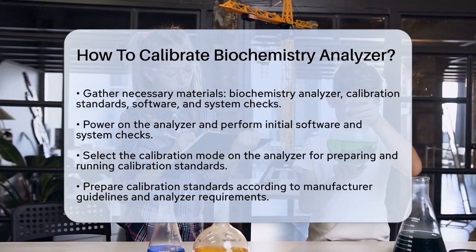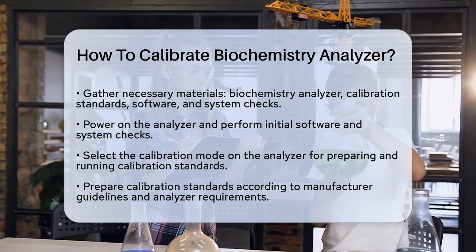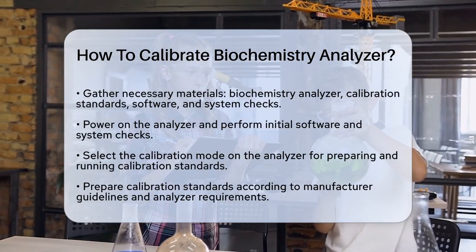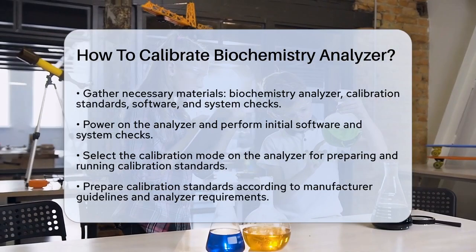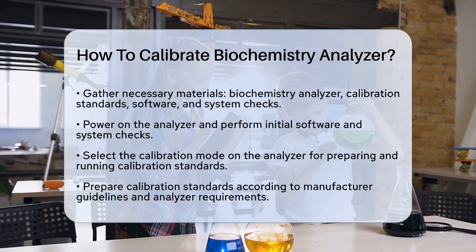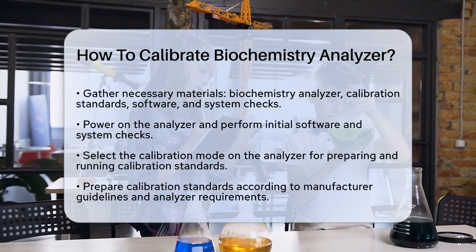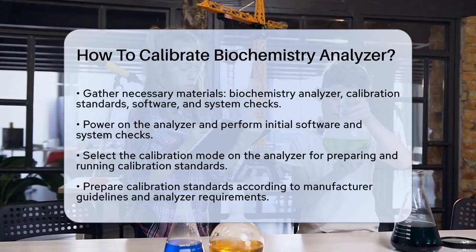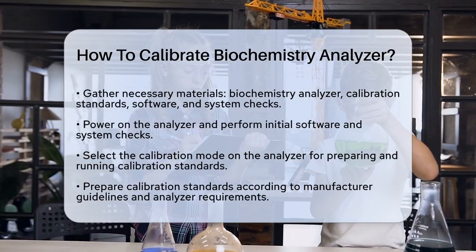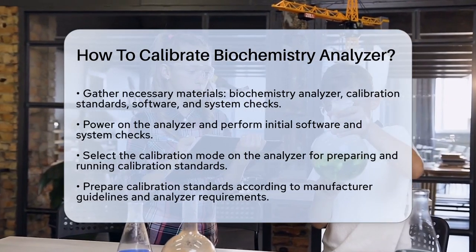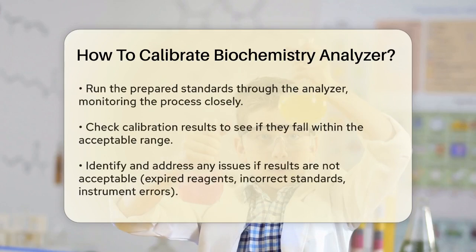Next, select the calibration mode on your analyzer. This mode allows you to prepare and run the calibration standards. These standards are reference materials with known concentrations of analytes that help set the accuracy of the analyzer. Prepare these standards according to the manufacturer's guidelines and the specific requirements of your analyzer.